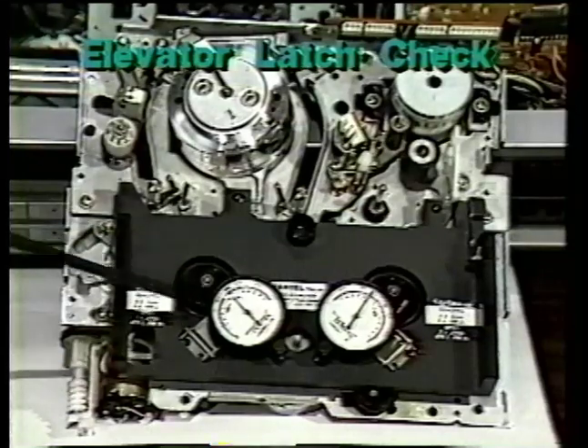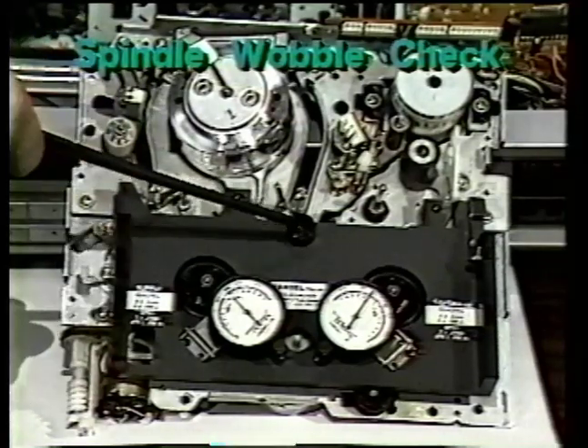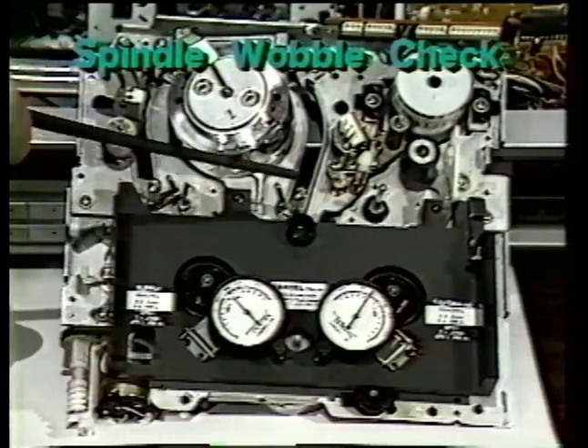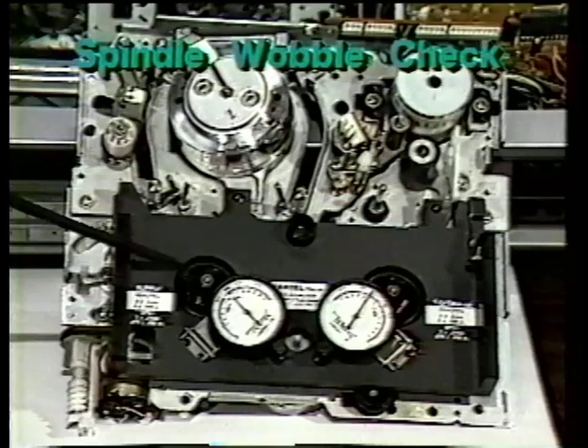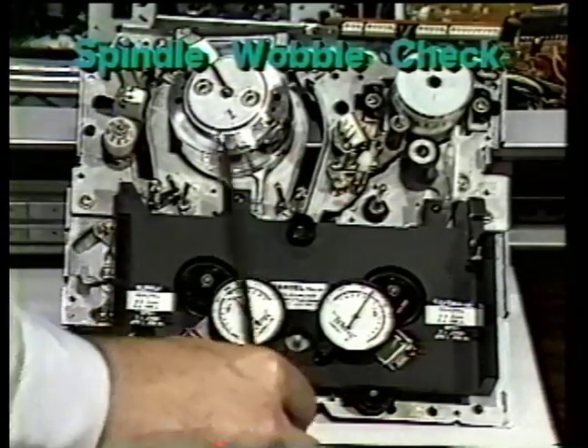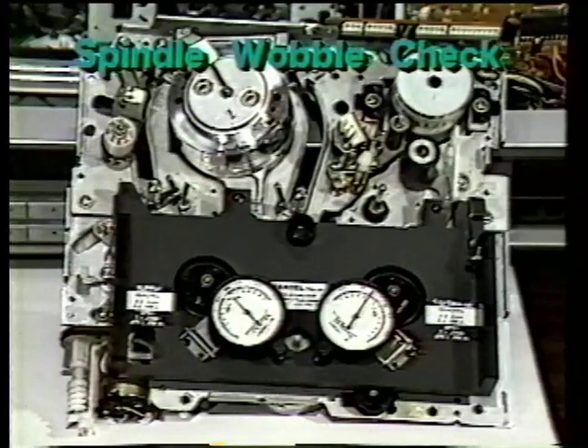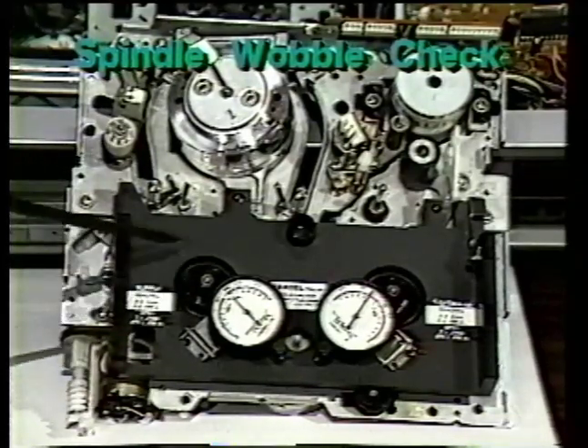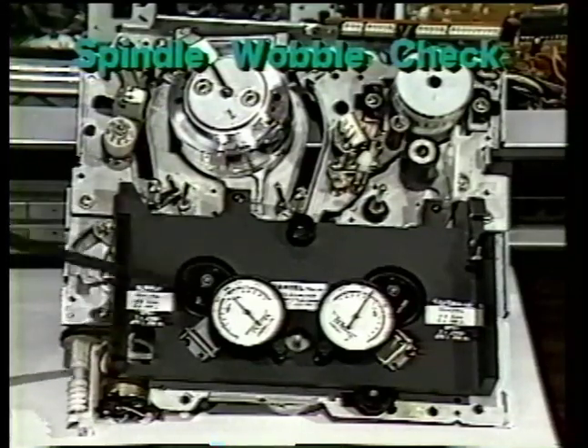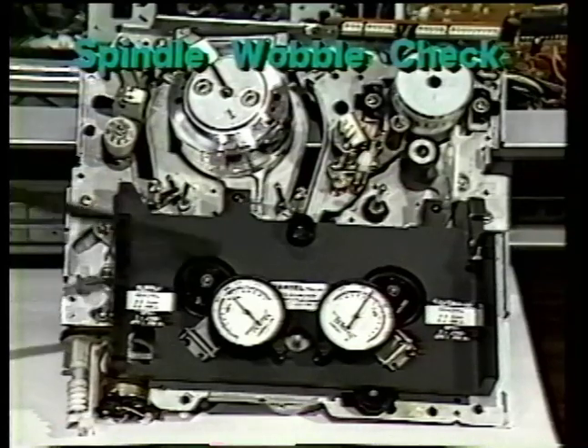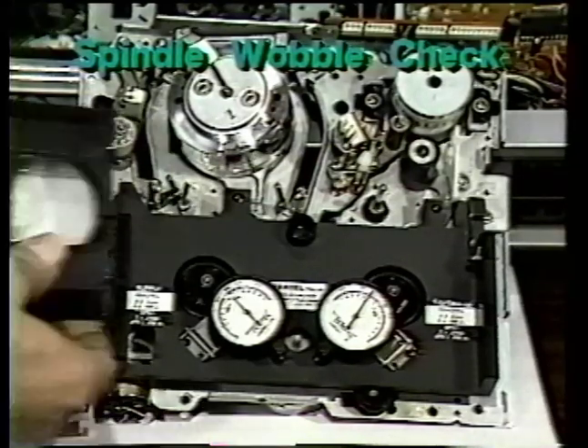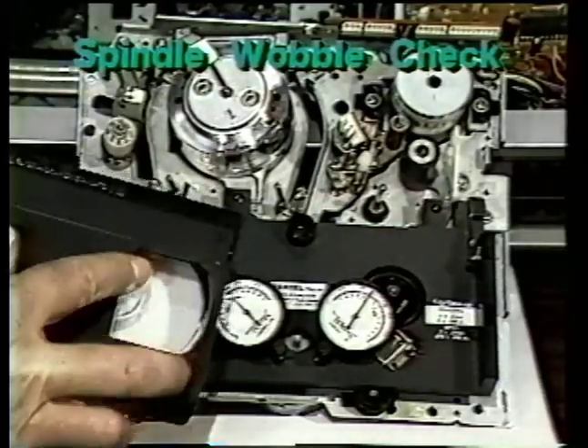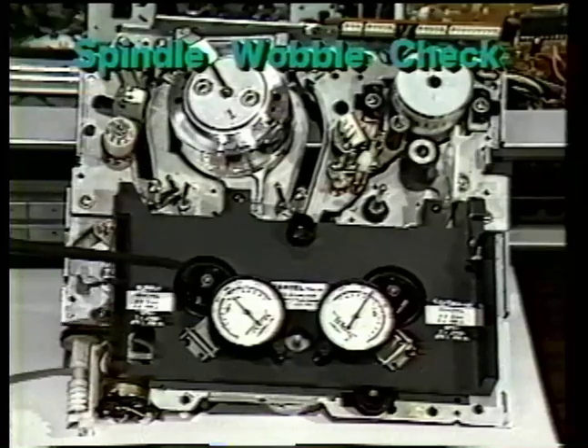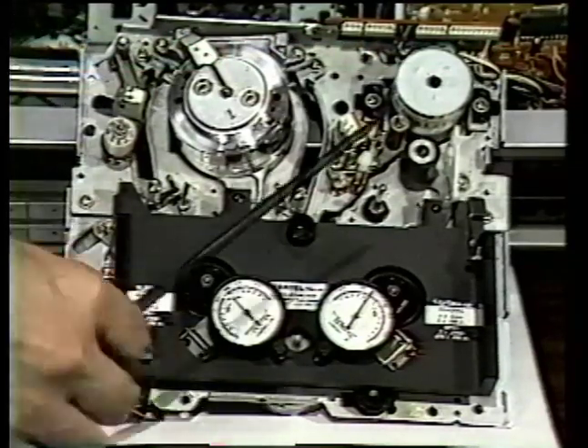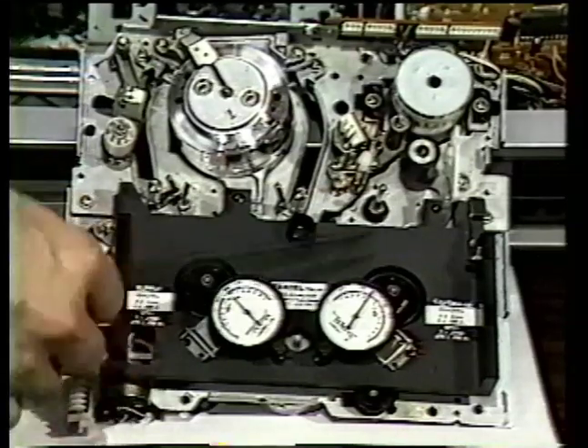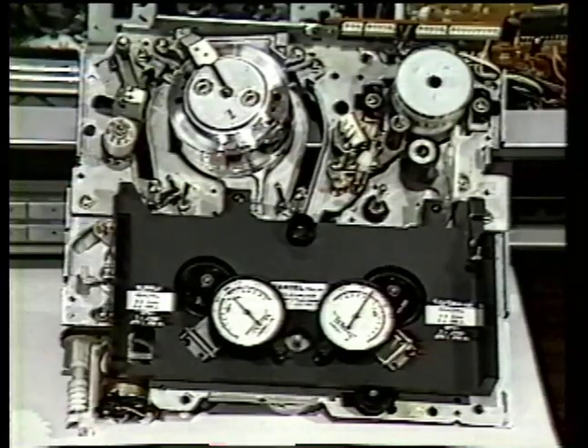The spindles can rotate as we go into fast forward or rewind. You notice we have a light blocking shield here so that we can put the machine in fast forward and rewind. It causes each of these spindles to rotate. If we then see an oscillation on the pointer, that would indicate that the surface that's supporting the reel is not rotating perpendicular with the axis of rotation, or has a lump or bump on the plastic surface itself. It would cause the reel in the cassette to sit off and then edge damage again. So we want to be able to put it in fast forward and rewind and not see more than about 1 or 2/1000ths of oscillation when these spindles are moving under the test measuring points.